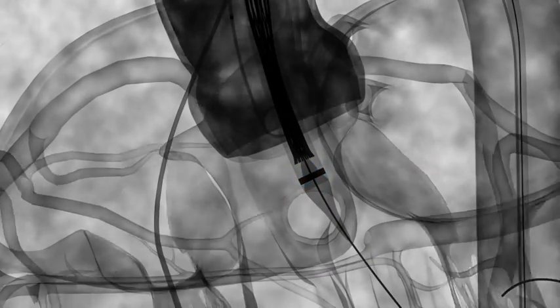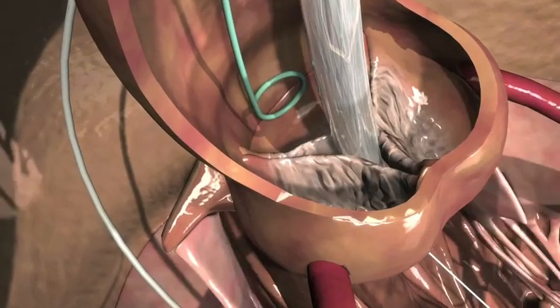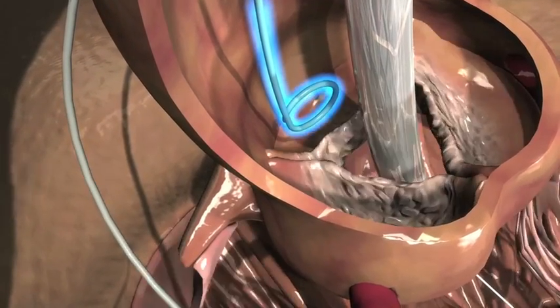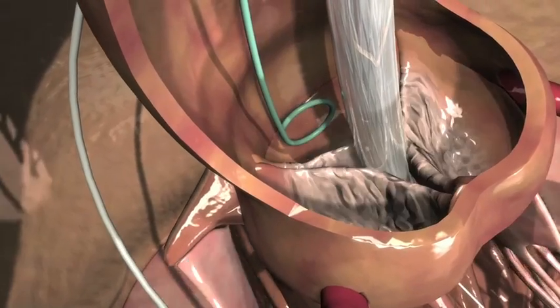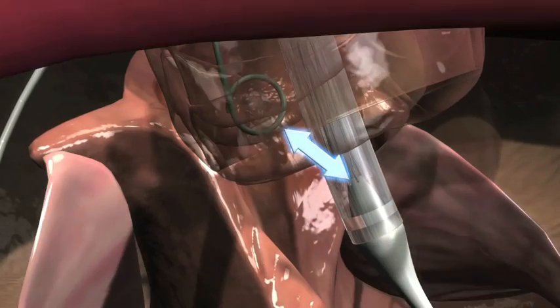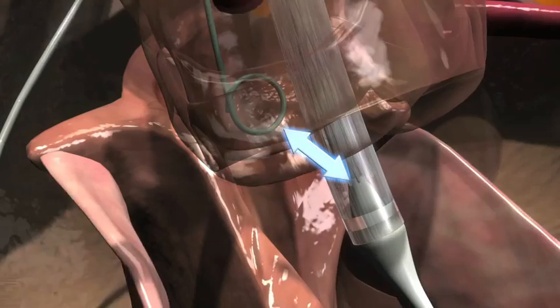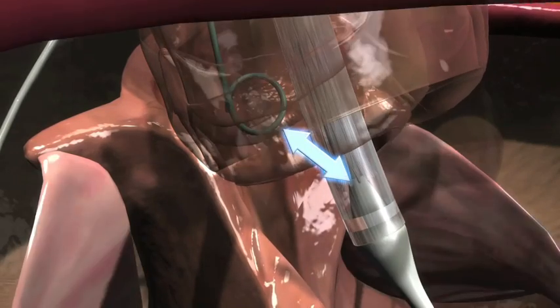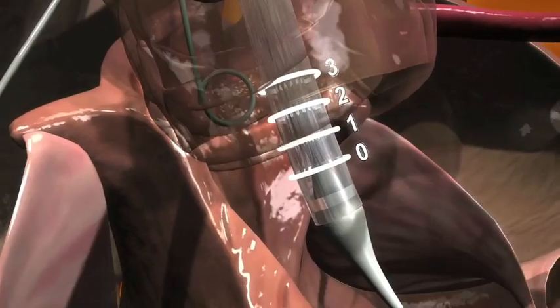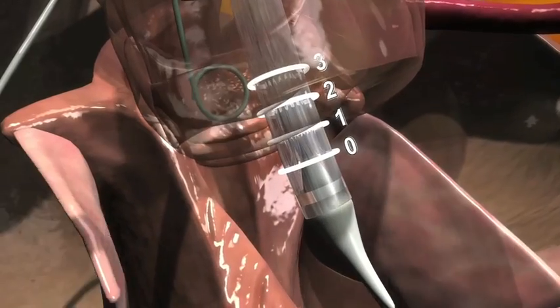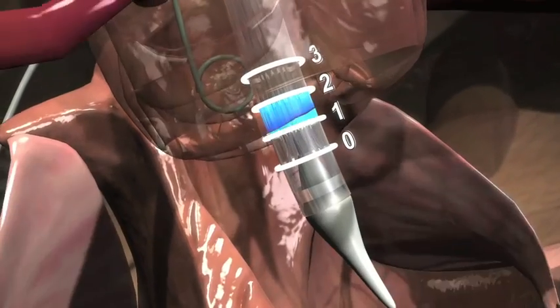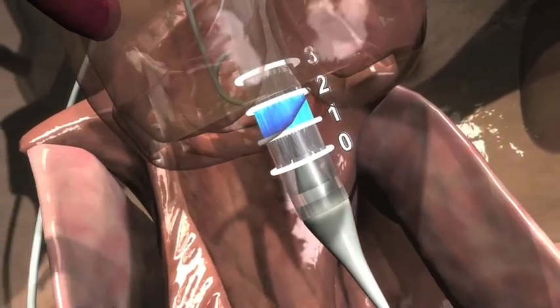Perform an angiogram. Confirm that the pigtail catheter is still within the non-coronary cusp of the aortic root. At this time, visually identify the distance between the base of the aortic root and inflow edge of the valve frame. Now, let us take a closer look at the crimped valve. Note the radiopaque contact points. Counting from the inflow edge of the frame, optimal placement of the valve is the shaded area between the first and second contact point implanted within the aortic annulus.